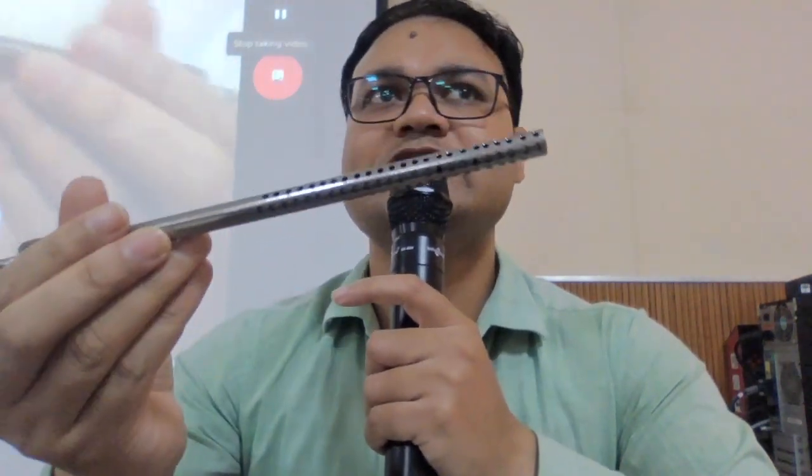If otherwise only a single tube is there and it gets blocked, then you have to dismantle it, take out the blockage present inside and use it again. That is a problem when a single tube is there. So this tube-within-a-tube structure helps in preventing frequent blockage of the suction cannula. It is used for suctioning blood, secretions, pus from the operative field.